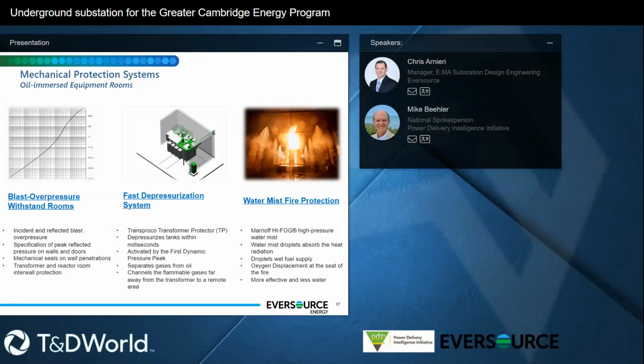That starts to wet the device, but they're also directly focused on where the fuel system is coming to deplete the oxygen or displace the oxygen to mitigate the fire. The huge advantage of this is it's like a tenth of the amount of water that's generated from a deluge system. So when you think about an indoor below grade substation with an oil containment, to minimize the amount of water that could be put into your oil containment, if your transformer did let go oil as well, we're less concerned about the water overflowing and spilling and causing like an oil slick on the main floor, because now we're generating very little water to put out the fire. And if the oil does, the oil truly with the water will stay contained into the transformer bay.